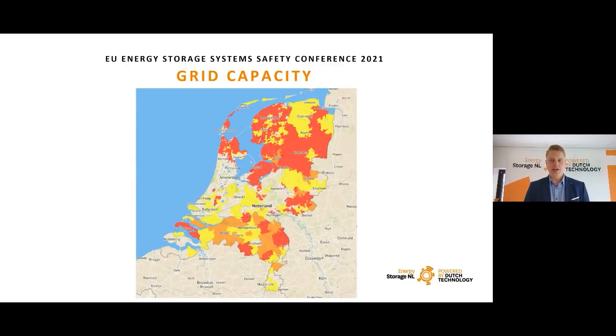What we see here is actually the issue with grid capacity in the Netherlands at the moment. We've seen a very rapid increase of solar PV generation, especially in areas outside of the cities, which typically are farming areas and don't have a very strong electrical grid. There's not a lot of electricity demand, so all this new solar PV generation cannot be fed into the relatively small grid available in these areas.